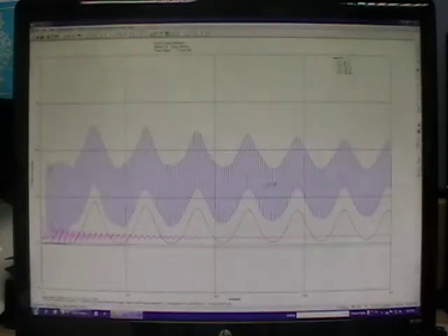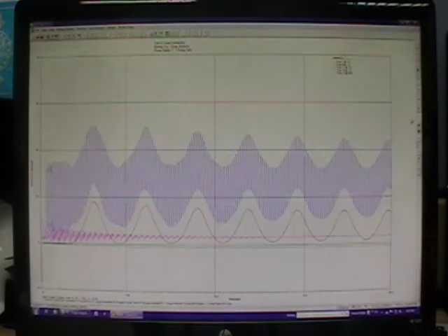Okay, we'll stop that and we'll look at the results which have been post-processed earlier from the actual project. So she's just going to open up the plot, which shows the transient pressure plot. And here, those spikes that you see at the beginning was what we saw live just now. And there's a pattern to it as the flow comes in. Now those patterns are superimposed on the spikes. So it's a complex situation, and we had to analyze that.